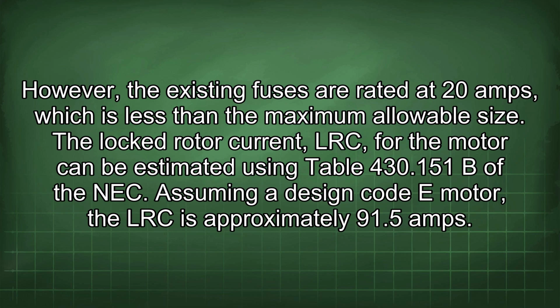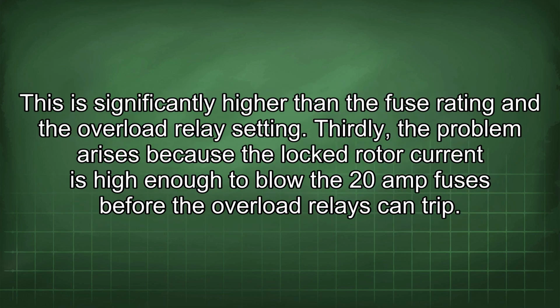The locked rotor current, LRC, for the motor can be estimated using Table 430.151(B) of the NEC. Assuming a design code E motor, the LRC is approximately 91.5 amps. This is significantly higher than the fuse rating and the overload relay setting. Thirdly, the problem arises because the locked rotor current is high enough to blow the 20 amp fuses before the overload relays can trip.